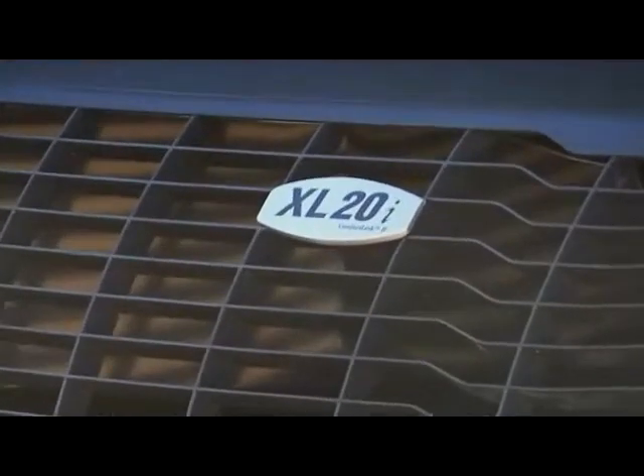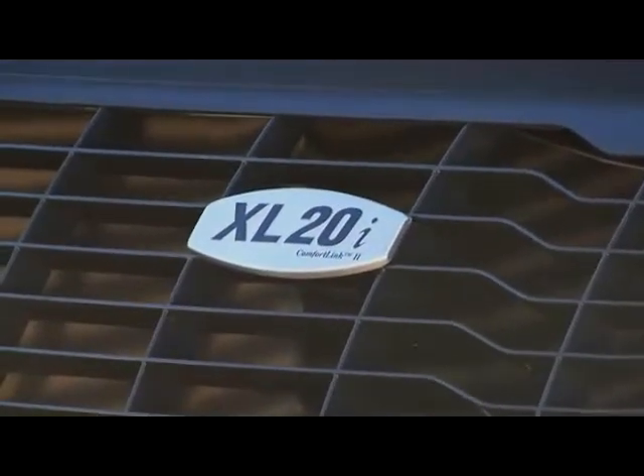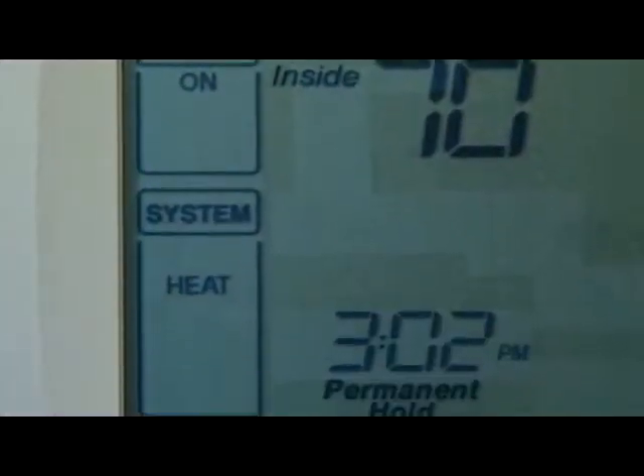The higher efficient units have to have larger heat exchanger surfaces in order to get the heat exchange process to operate effectively. Where previously we had 2 heating zones, in fact 2 complete different heating systems, we now have 1 heating system with a single zone controlled by the Trane Comfort Link 2 control system. That system, because of the better envelope, allows us to maintain better comfort within the house at far less use of energy.